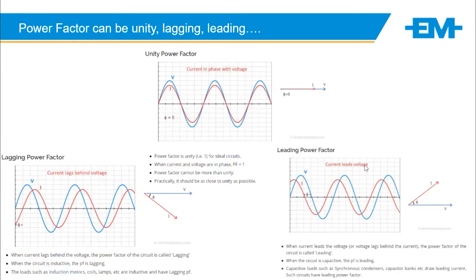Then we have what we call leading power factor. It's not common, but this would be if your circuit becomes too capacitive. You would see this if you had a faulty power factor bank and you go leading. LEDs can sometimes cause a leading power factor, but at a very low current, and so forth.